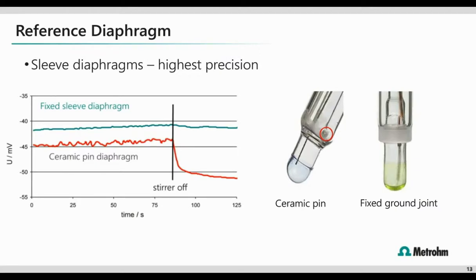So the diaphragm is the actual entire frosted section in the middle there. It goes all the way around the electrode. That's where the electrolyte will drain into the sample. Regardless of design here, the functions are the same. We want to slowly ensure contact between the sample and the reference electrode via the electrolyte solution.